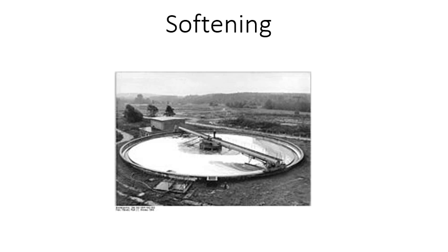The relationship between pH and alkali constituents in water. So this is how lime softening works. You are adding lime to raise the pH to convert these different constituents so that they will precipitate out. So you have CO2, which exists naturally in water as a dissolved gas. CO2 affects the pH and alkalinity as it forms carbonic acid, H2CO3, in water, which creates a demand on lime softening chemicals when present.